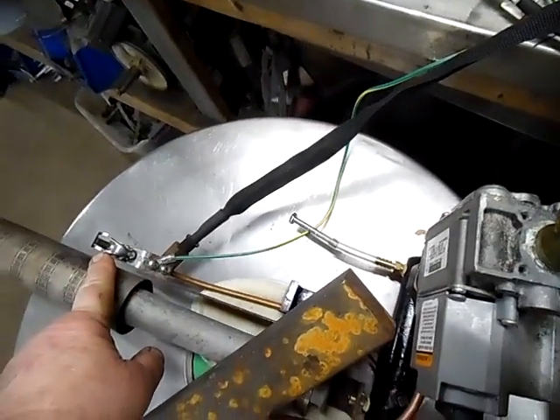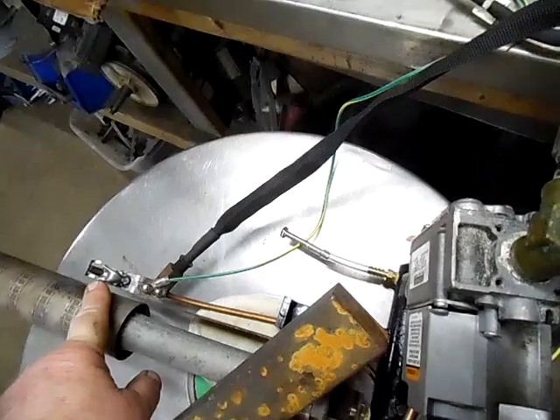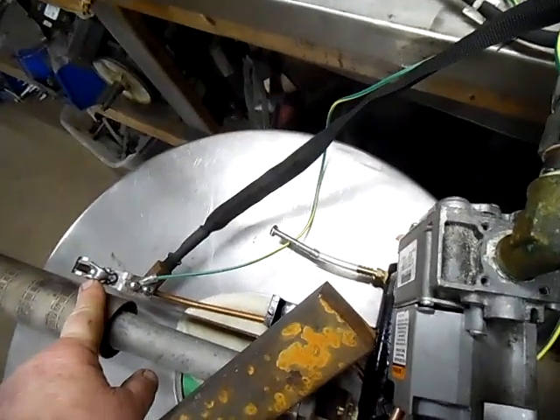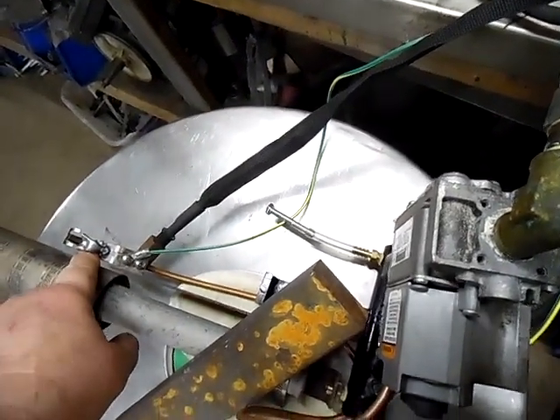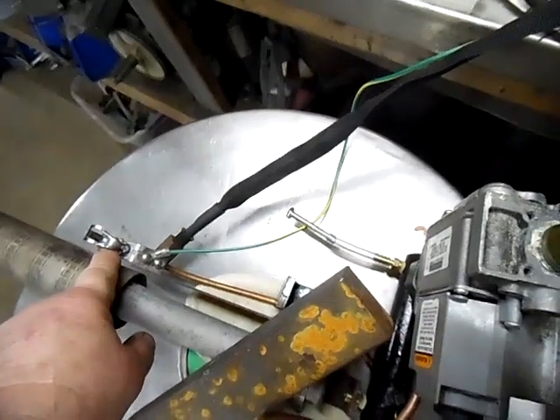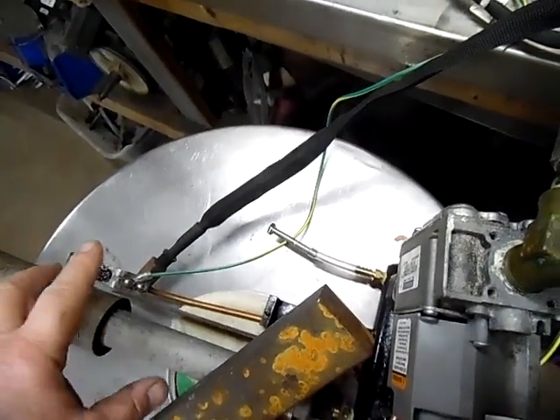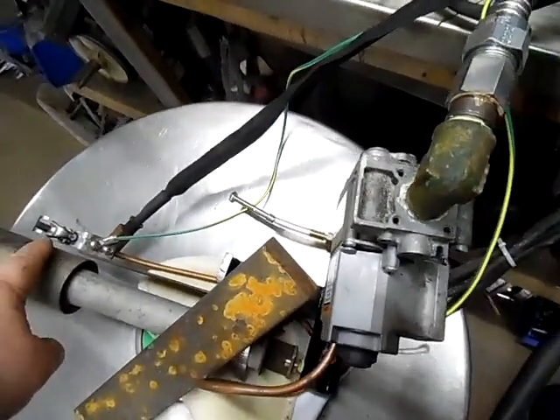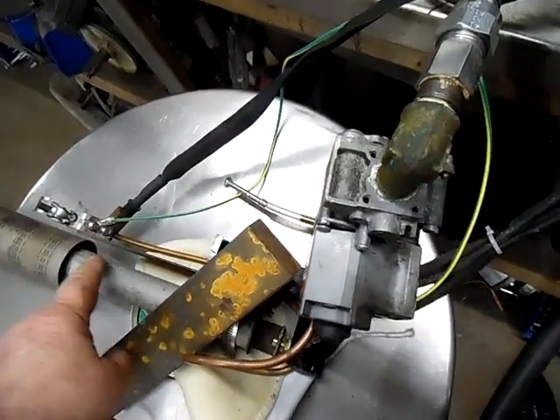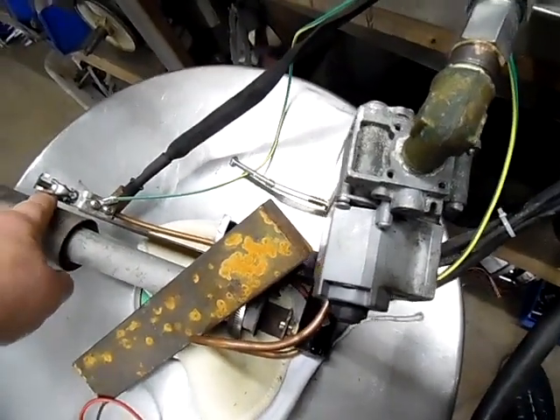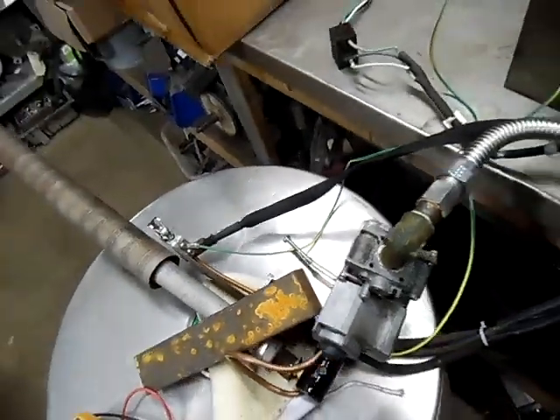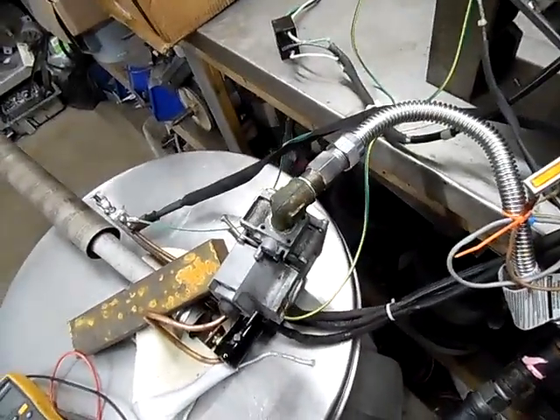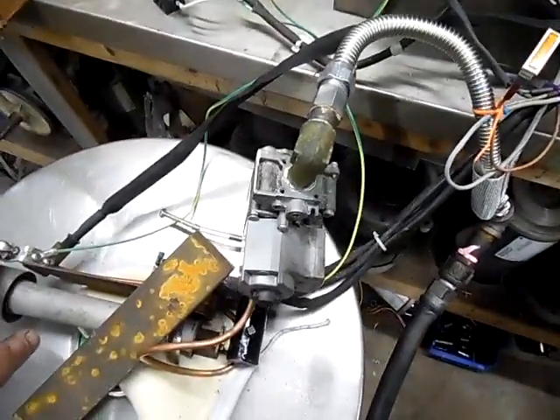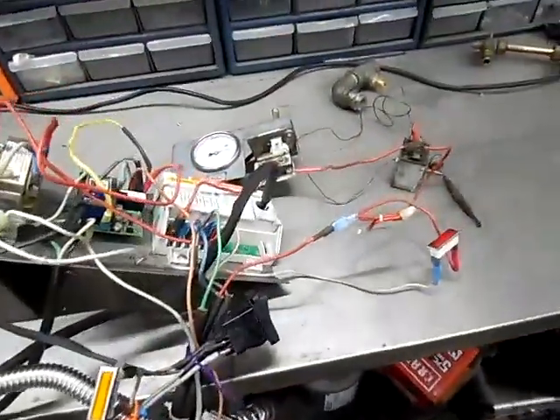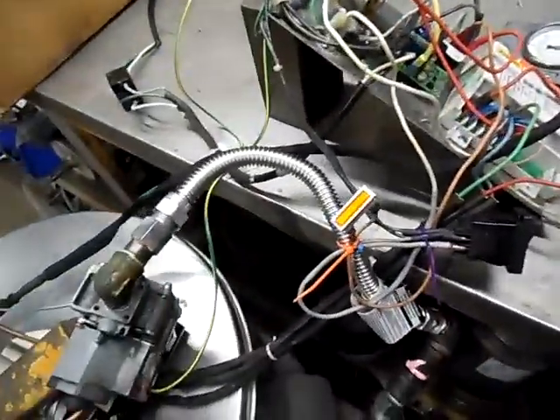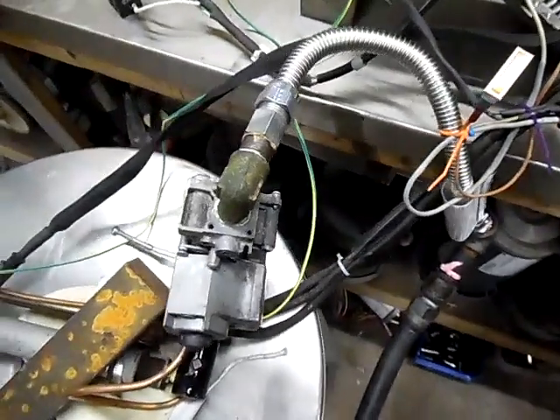Once that senses a flame, which usually happens within 1 or 2 seconds if you have a good flame, then the MV will get energized. That's your main valve from the box, and then your burners will start to light. The biggest problem we run into with these single rod systems is that they will not work sometimes. If you have a system where everything looks to be working okay, the pilot comes on, turns right back off, that's usually because the box is not reading the proper sense microamps from the flame.